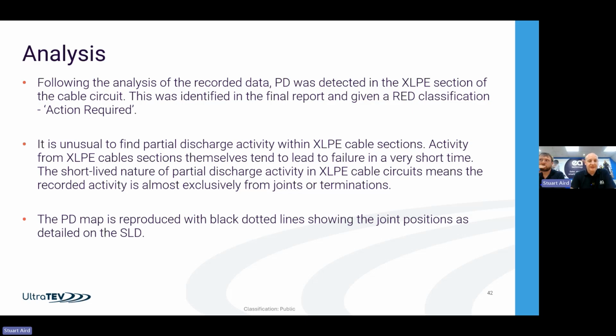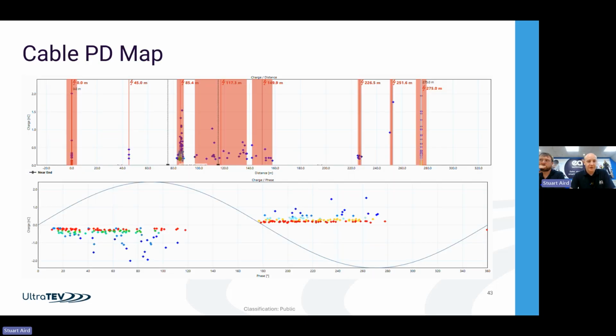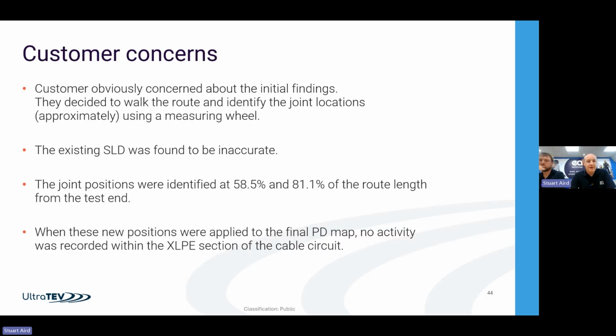But the worrying thing was it did indicate some partial discharge within XLPE sections of the cable. So I'll just show you that. These two lines here are the joints that were provided originally, and obviously all these dots are areas of partial discharge. So we went back to the customer and recommended they recheck where their cable terminations or joints are in the cable. The customer was concerned, so they walked along the cable route and measured where all the cable joints were. That indicated they're in a slightly different position to where they were originally.